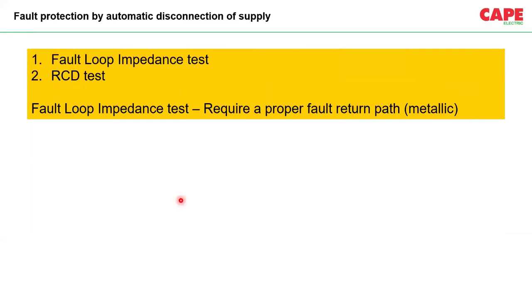Now, with respect to fault protection by automatic disconnection of supply, there are two tests required. The first test is a fault loop impedance test. With a fault loop impedance meter, you have to measure the impedance of the circuit. You have to establish the fault current, then compare the fault current with the disconnection time of your protective device. So you have to have a meter, you measure the fault loop impedance, you measure the fault current or calculate the fault current, then you compare it with your protective device and see that it is able to disconnect within the time specified.